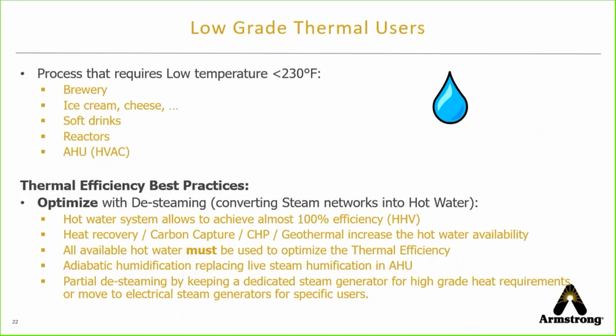And the way we look at it is that all available hot water must be used to optimize the thermal efficiency. But on the humidification side, many of us have a lot of air handlers, and some of us are using direct steam injection to condition the air in those air handlers. So we can take a look at potentially de-steaming air handlers through adiabatic humidification, and then use heat pumps or other forms of heat recovery to raise or lower, condition the inlet or outlet air from the air handler.